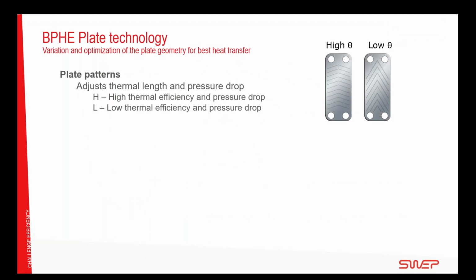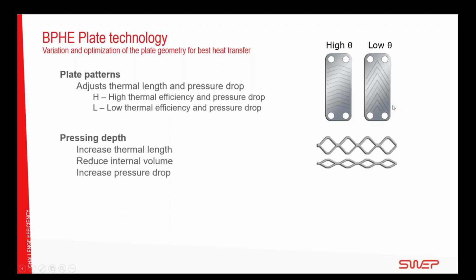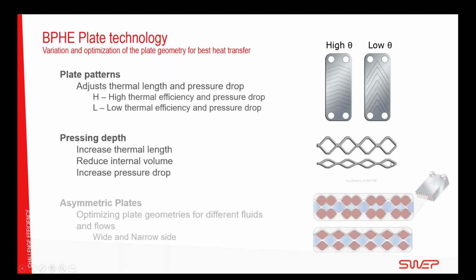How do we work with creating our heat exchangers? We work with high theta and low theta plates. High meaning high thermal efficiency, high pressure drop. Low meaning low thermal efficiency and low pressure drop. We have products with a large pressing depth and a low pressing depth. Large pressing depth means less thermal efficiency, lower pressure drop. The opposite is true for the tight channels, that is higher pressure drop and higher thermal efficiency.